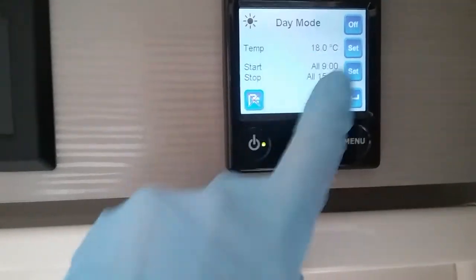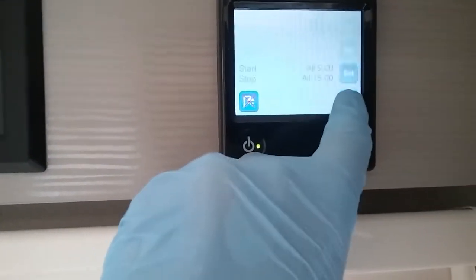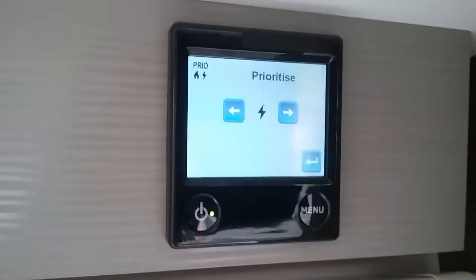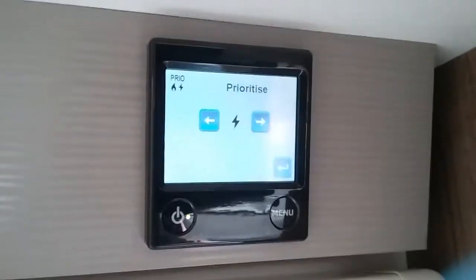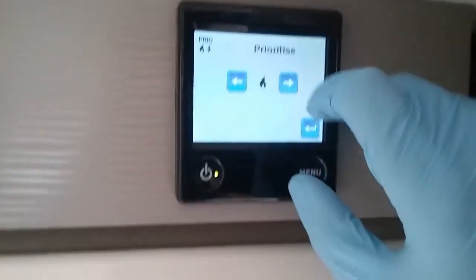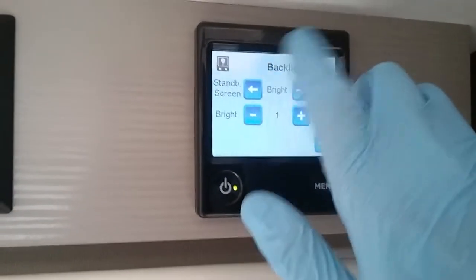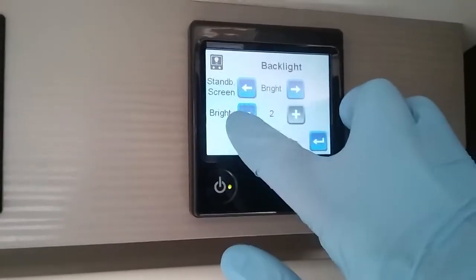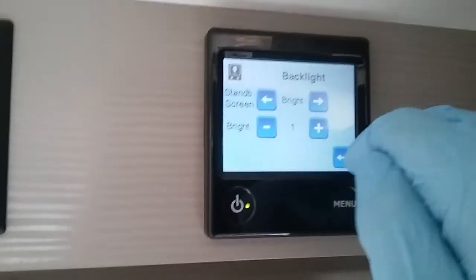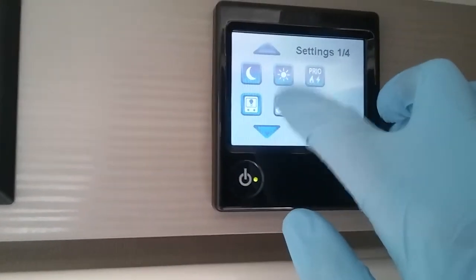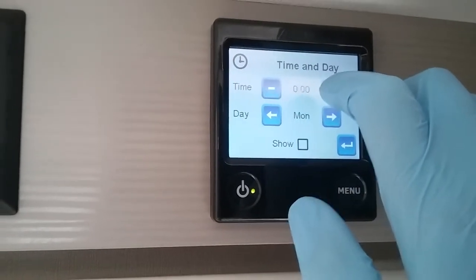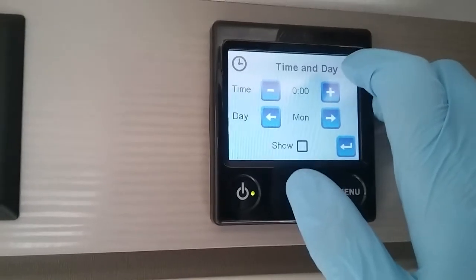Next we have virtually the same again but for the daytime. Then we have a setting that prioritises what the system uses when in dual fuel mode — at the moment it would favour main supply over gas. If you were on an extremely low amp site you can flip it so it consumes more gas and less electricity. Next we have brightness of the screen, you can invert the backlight all the time if you wanted to. One option is not used on this particular model, and then this one here is the clock — set time of day for when you're using both day and night modes.